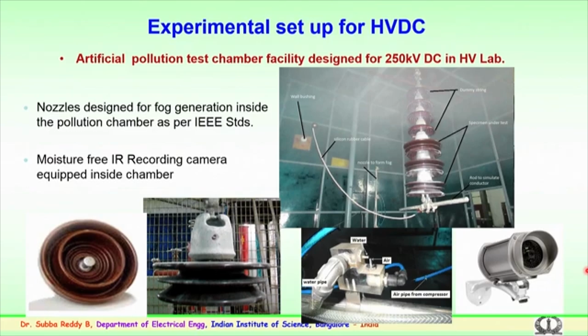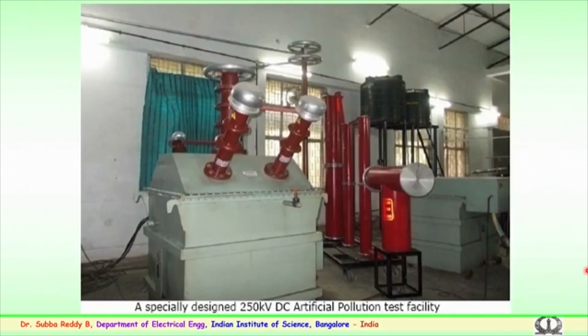activity inside the chamber. Various experiments have been conducted on single discs, 3 discs in a string, and 6 insulators in a string, because the facility can cater up to 250 kV.